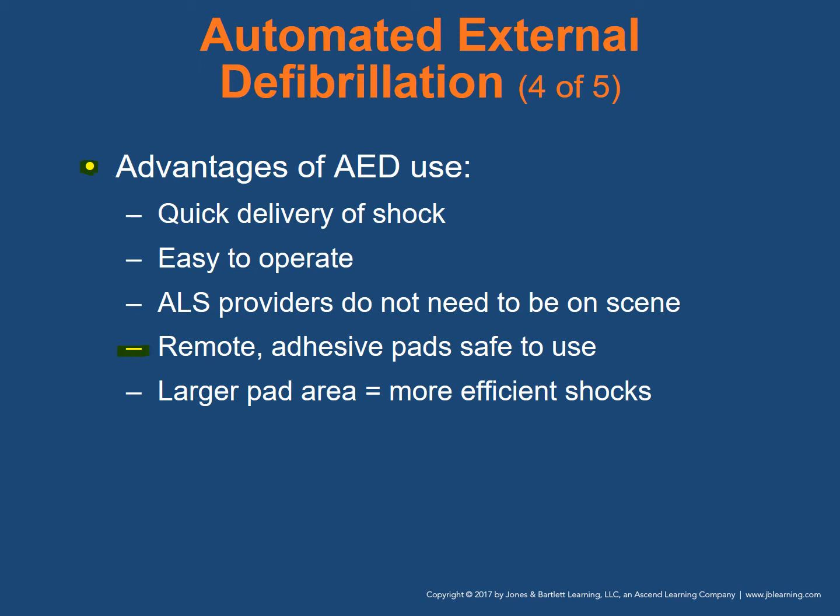And so they could very easily slide off of the patient's chest, or when providers were rubbing the paddles together, they could accidentally discharge the electrical energy, and that would arc in front of their face, and it could give them really severe burns, or in really severe situations, it could actually kill the patient. So the fact that we have these adhesive pads that are basically big stickers that we can put on the patient's chest means that once we place them, theoretically they're not going to go anywhere. And once you place those pads, it's really hands off. You don't need to touch those pads anymore where the electrical energy is moving. And the larger pad area equals more efficient shocks.